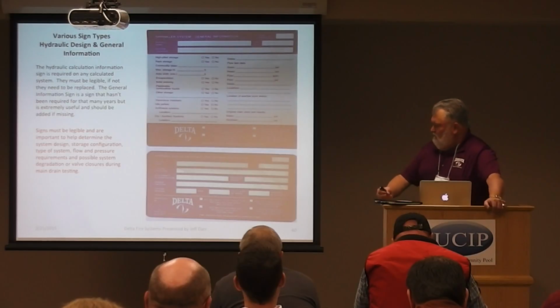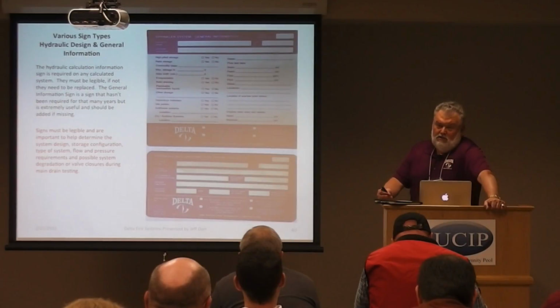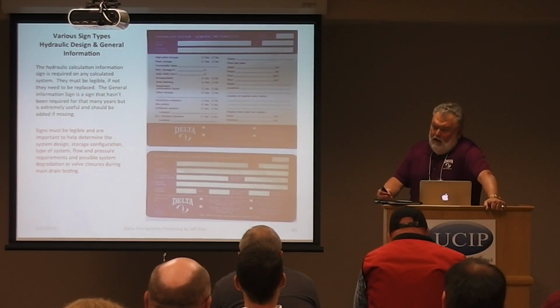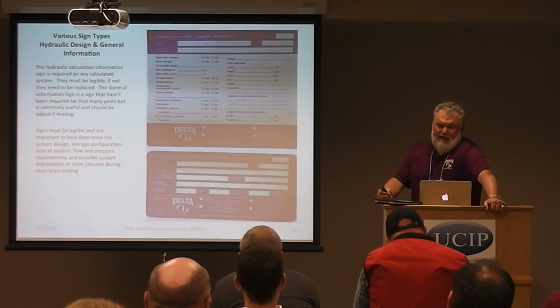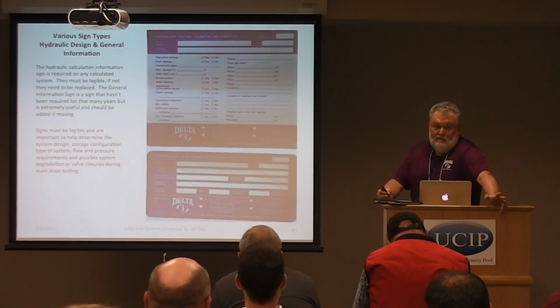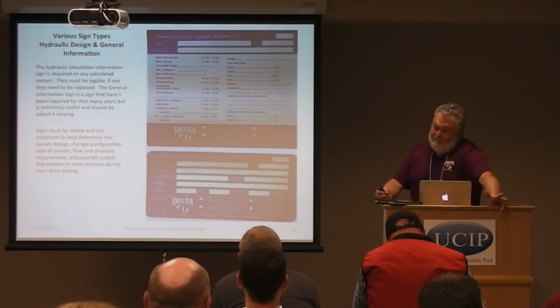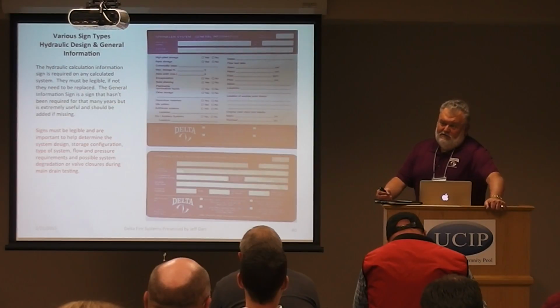We call it a hydraulic calculated sticker, and it's required to be on any hydraulically calculated system. I would say from 1980 forward, the majority of systems are hydraulically calculated. Before that, they had what they call pipe schedule systems, where so many heads were required on certain size pipe. 2 heads was 1-inch pipe, 3 heads was 1.25 inches. Those things have gone by the wayside, and we still run into them occasionally. But just be aware that they're out there.